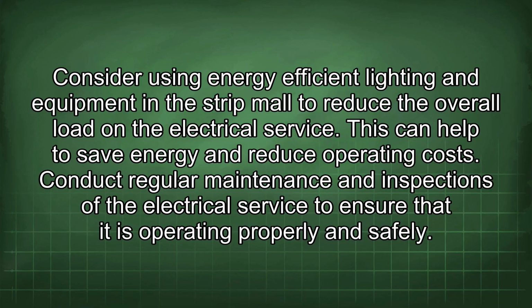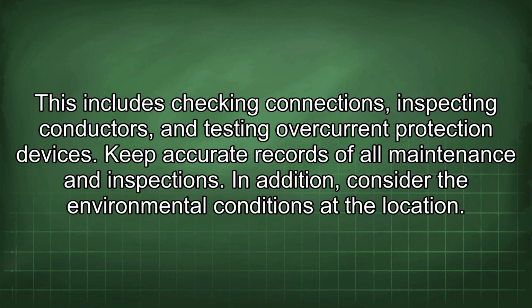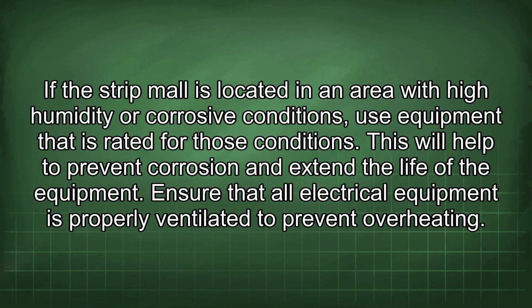Conduct regular maintenance and inspections of the electrical service to ensure that it is operating properly and safely. This includes checking connections, inspecting conductors, and testing overcurrent protection devices. Keep accurate records of all maintenance and inspections. In addition, consider the environmental conditions at the location. If the strip mall is located in an area with high humidity or corrosive conditions, use equipment that is rated for those conditions. This will help to prevent corrosion and extend the life of the equipment.